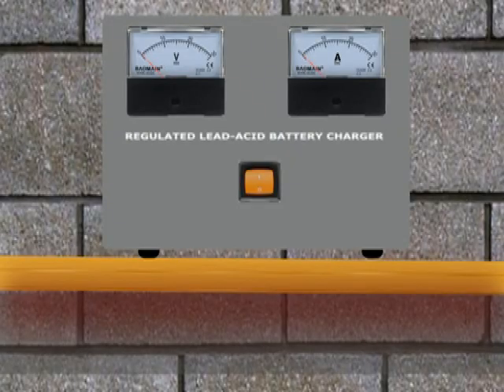To limit the number of charge and discharge cycles, an additional charger can be used, powered by the power company network, for keeping the batteries in trickle charge all night. The charger should turn off automatically during the daytime and give way to the solar panel system. The transition should not cause any flickering in the power output so as not to affect computers and other sensitive equipment.